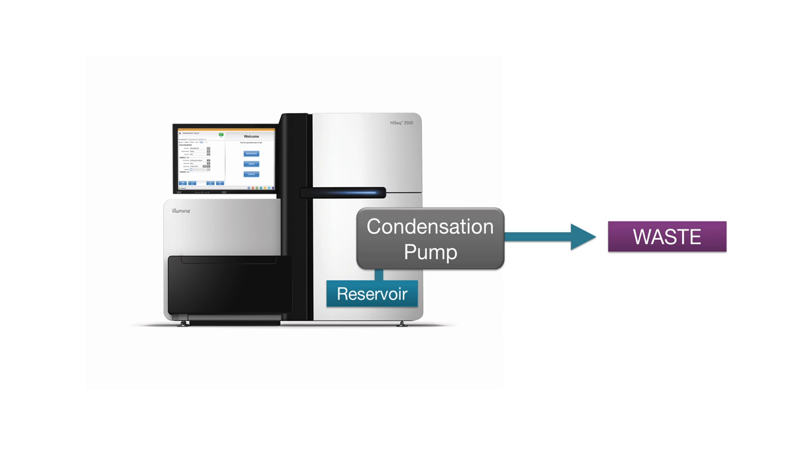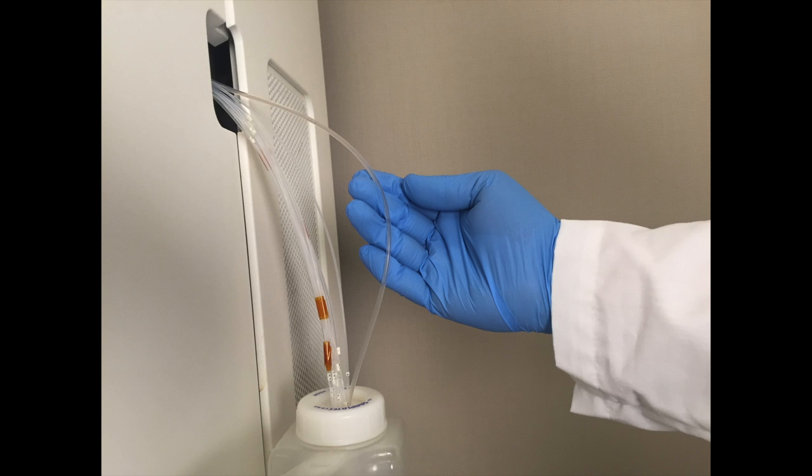You will hear a clicking sound daily coming from your HiSeq. That's the condensation pump. It drains the liquid from the reservoir in the back of the chiller to waste. The condensation pump waste line is the one that is thicker than all the other lines.